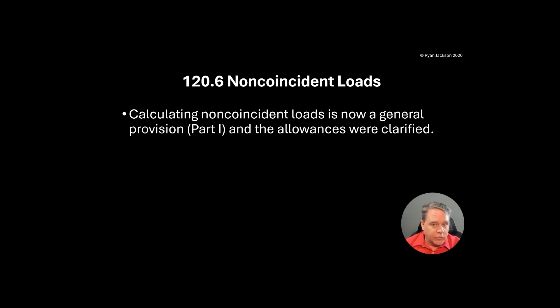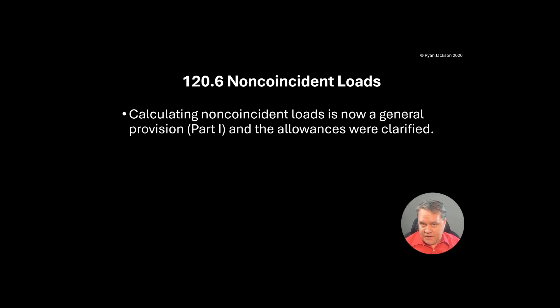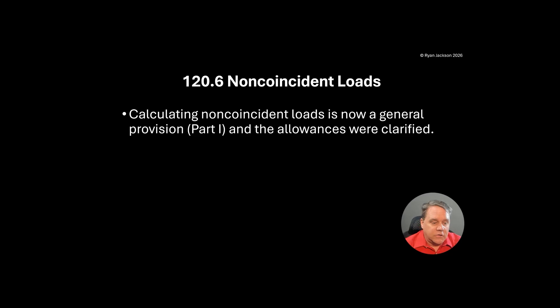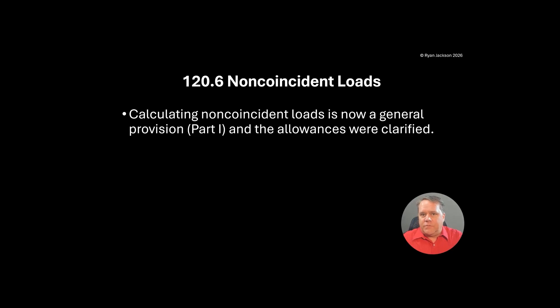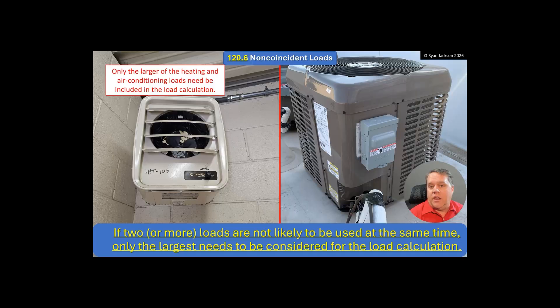Number one, they clarified it, which is great. But number two, by relocating it from 220.60 to 120.6, it no longer applies only to feeders and services. When you go to the 2023 code book and you look up non-coincident loads, it's in 220.60, which is for feeder and service calculations. This concept should apply generally — it's not something that's unique to feeders and services. It's something that could apply to anything. So by relocating it, that in and of itself is a technical change in this instance. A lot of times when you move something, you just changed the numbers. Now this actually means something.